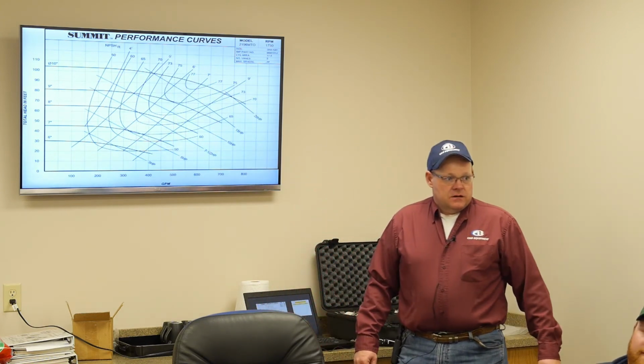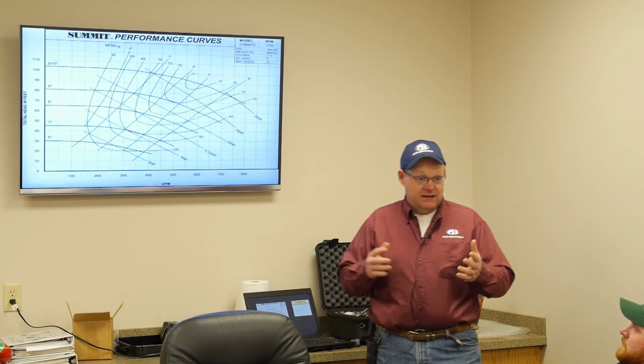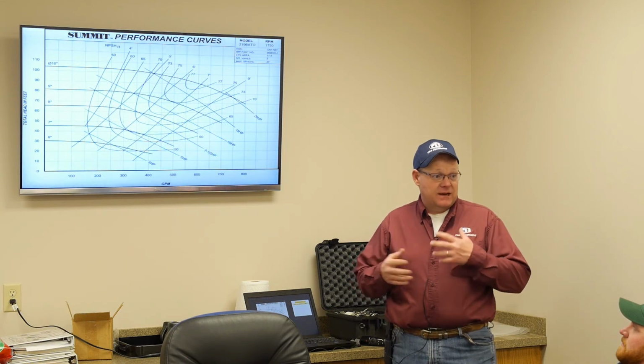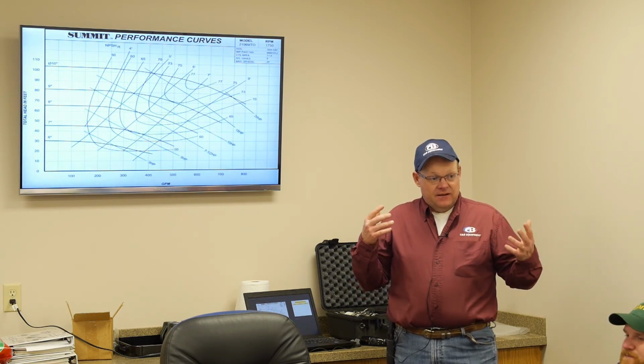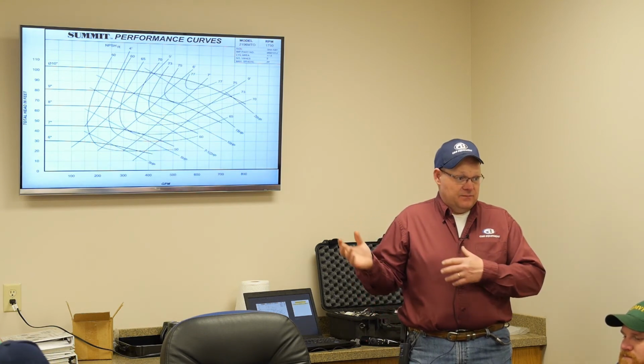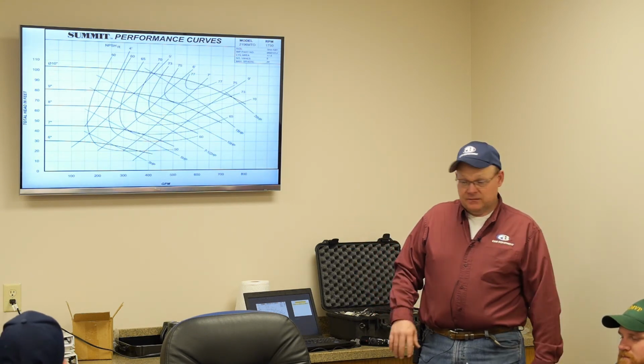So, very good point. Will that do the same thing if you change the vanes? Yeah, you start adding vanes or decreasing vanes. You increase the velocity or decrease the velocity. Same principle. Like the Gorman-Rupp, if you guys want to, we'll get a Gorman-Rupp impeller and I'll show you. It just has 2 vanes. Terribly inefficient, nasty looking old rough castings. They're just designed from point A to point B. What is exact? Probably your Jaegers and MPs and Flowmaxes and stuff like that really don't have a finished casting to them as much as they're just trying to get stuff from point A to point B. Transfer pump. It's not a true process pump.